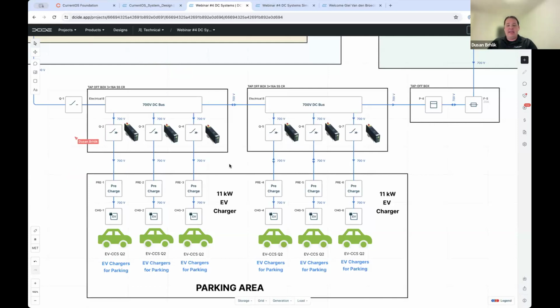So you said this entire system is controlled by droop control, and if I understood you correctly, you have one voltage for the entire bus. If more energy gets put into the bus, the voltage goes up, and if too much energy gets sucked out that the system cannot support, the voltage goes down. That's the guiding principle, and it effectively controls how loads like an EV charger react to keep the bus stable. I think that's fairly brilliant.